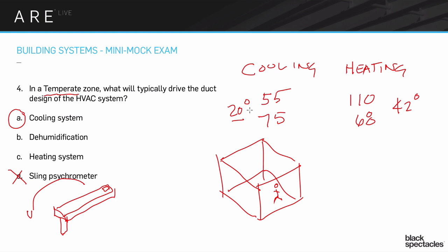So if it's going to be much harder to do for cooling than it is for the heating, that means the harder one is going to rule. And I'm going to have to define all my choices through cooling. So the size of the duct is actually going to be sized for a cooling system, and then you just kind of know that the heating system will work because the duct is going to be bigger than what it would actually be needed for the heating system.